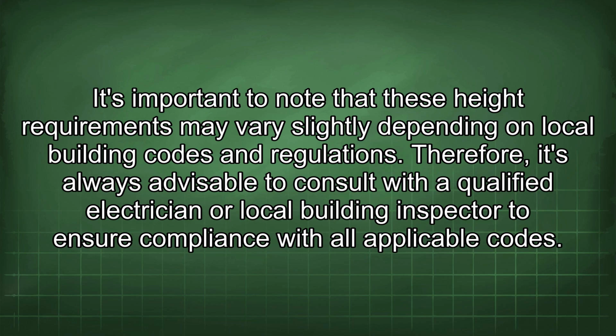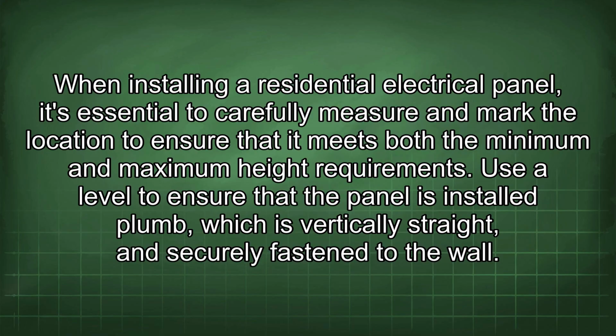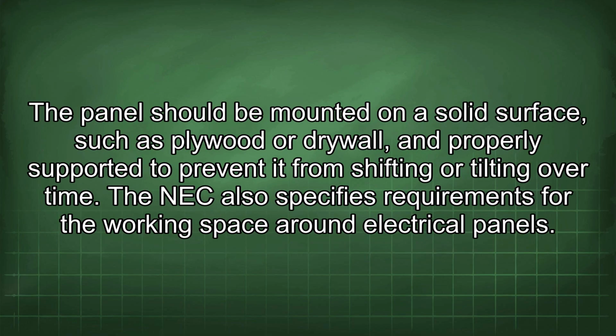When installing a residential electrical panel, it's essential to carefully measure and mark the location to ensure that it meets both the minimum and maximum height requirements. Use a level to ensure that the panel is installed plumb, which is vertically straight, and securely fastened to the wall. The panel should be mounted on a solid surface, such as plywood or drywall, and properly supported to prevent it from shifting or tilting over time.